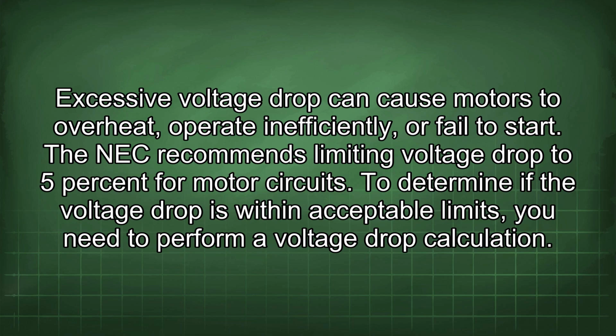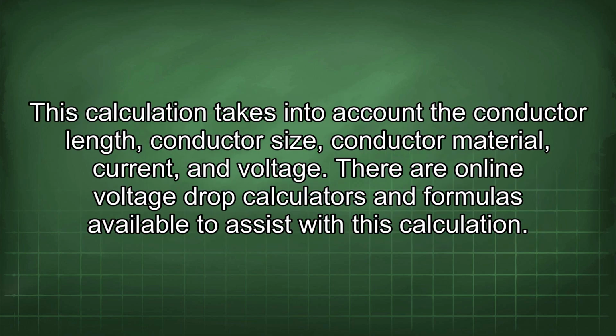To determine if the voltage drop is within acceptable limits, you need to perform a voltage drop calculation. This calculation takes into account the conductor length, conductor size, conductor material, current, and voltage. There are online voltage drop calculators and formulas available to assist with this calculation.